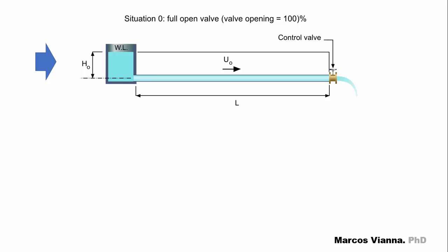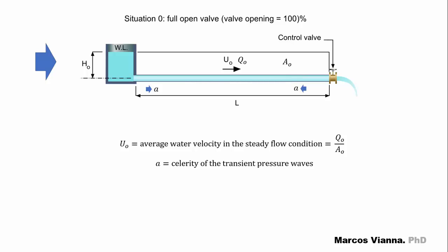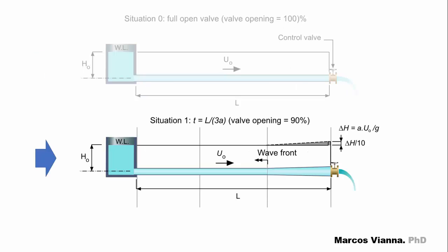Here we can see the water flowing in steady state. U0 is the average water velocity in its steady flow condition, and A is the celerity of the transient pressure waves. Now let's figure out what happens when we close the valve more slowly. We'll assume that the average velocity varies linearly with time. L over 3A seconds after the beginning of the closure operation, the wave front travels L over 3 from the valve to the reservoir. Let's assume that the valve opening is now 90% — 80%. This will be the configuration of the piezometric line along the pipeline.